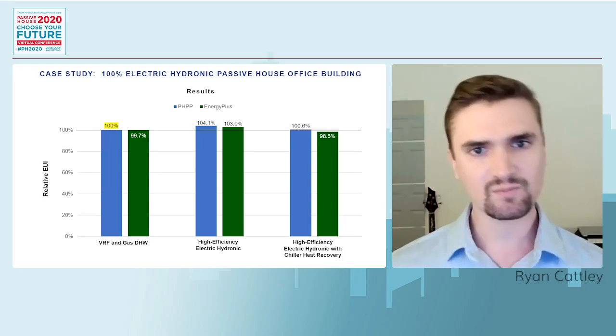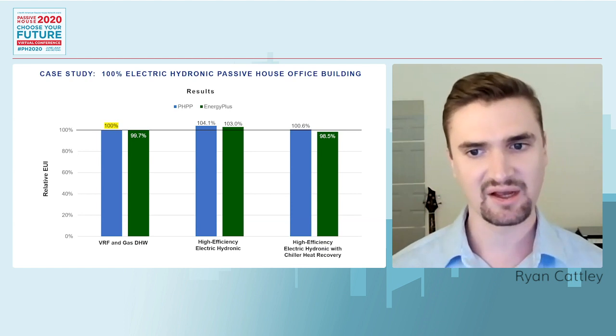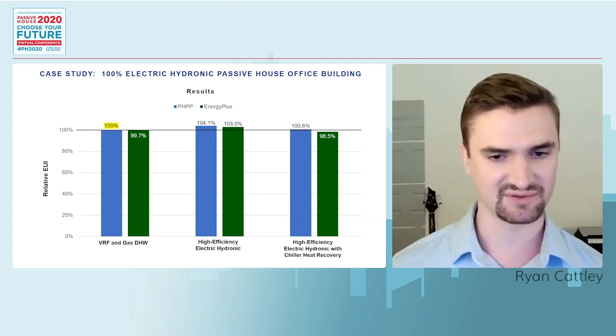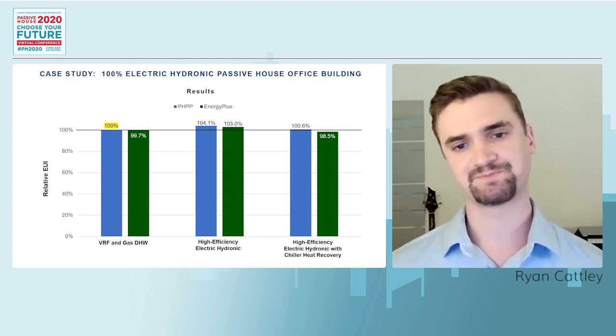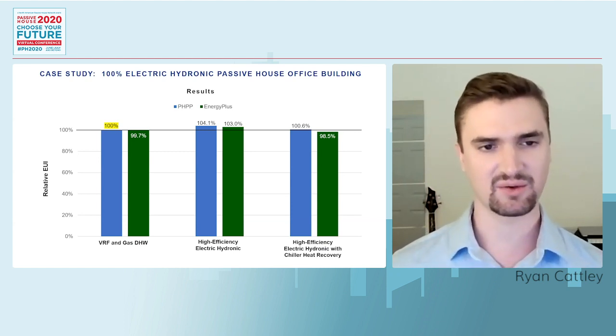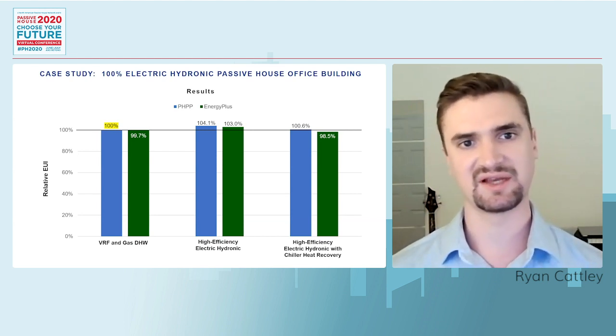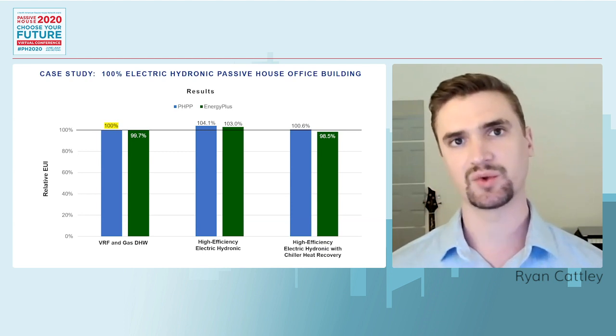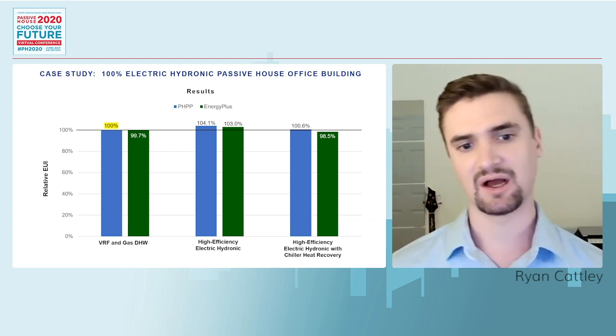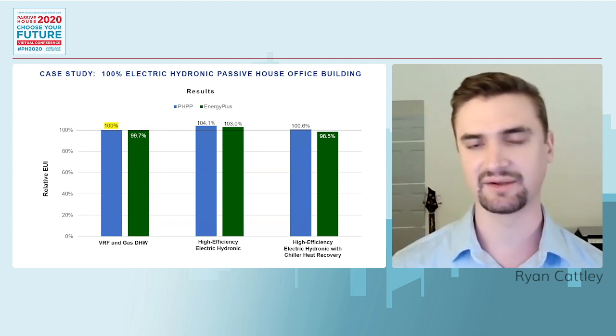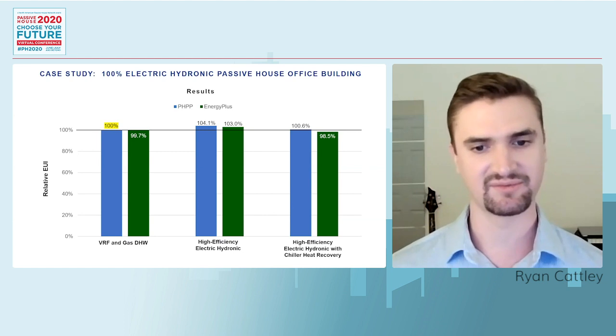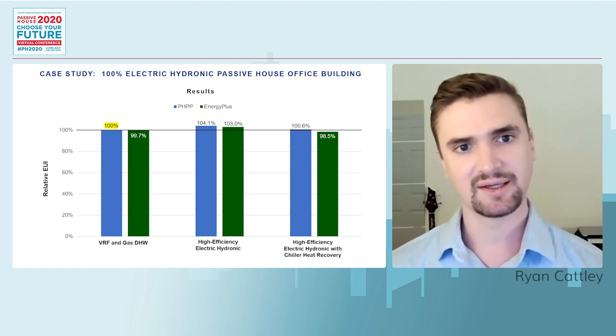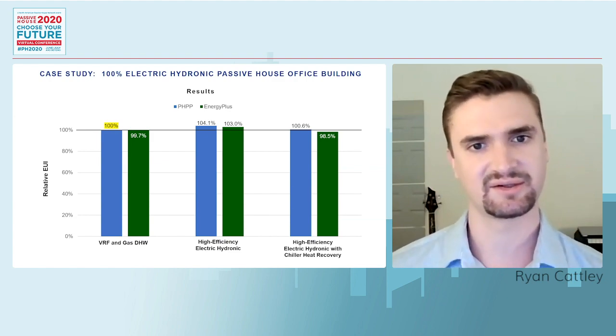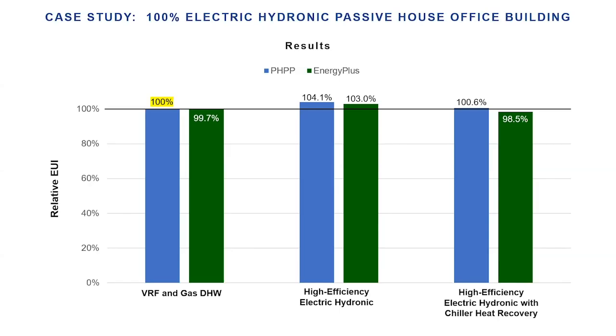So this case is important because while this case study does focus on a passive house quality envelope in an office building, this case in the middle is more aligned with something you may see in a multifamily residential building, where you don't have that simultaneous heating and cooling, because in the wintertime there's very little internal heat gain typically that you would find in a residential building, at least compared to an office building. And finally, the last case here is taking into account the heat recovery from the chillers. So we're using the chiller heat rejection to help heat the building in the shoulder seasons and in the wintertime.